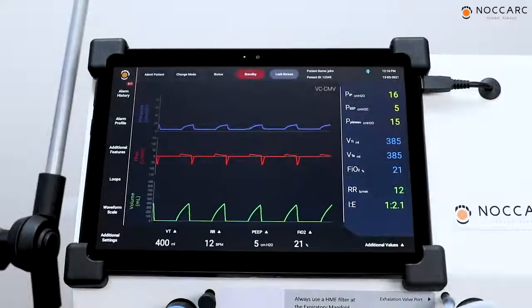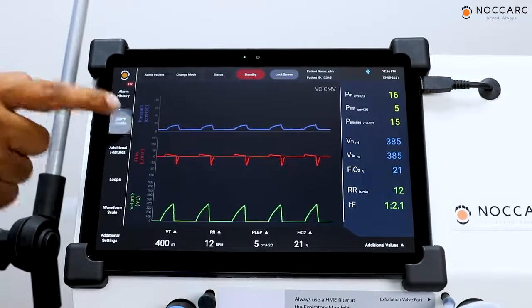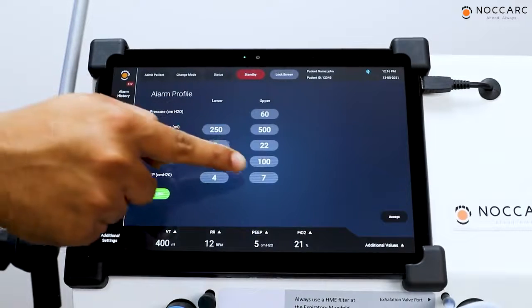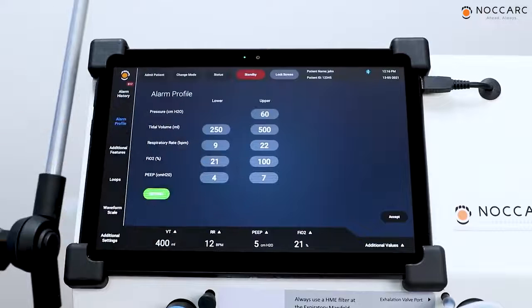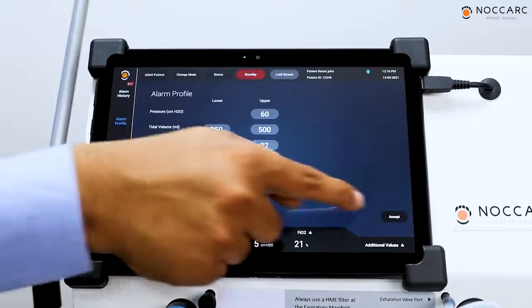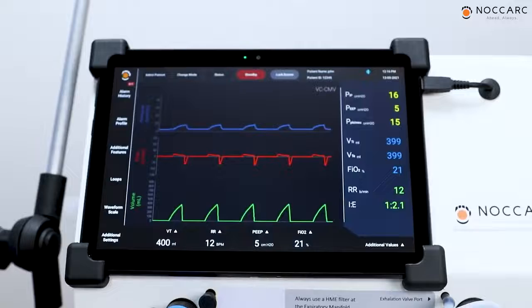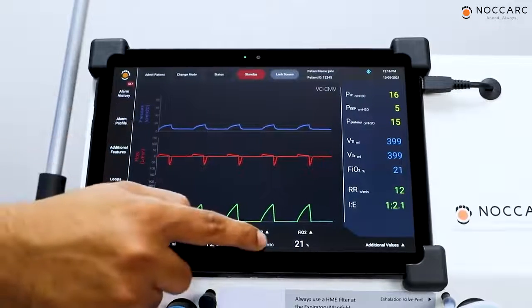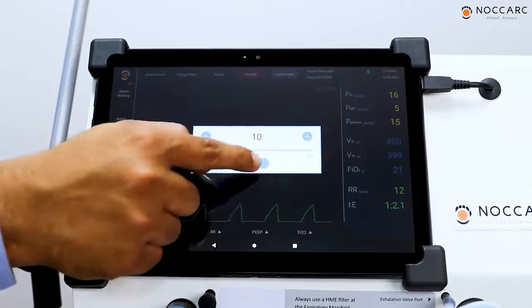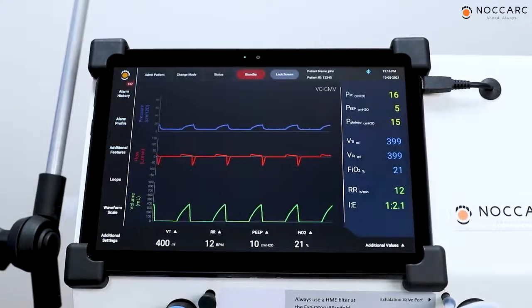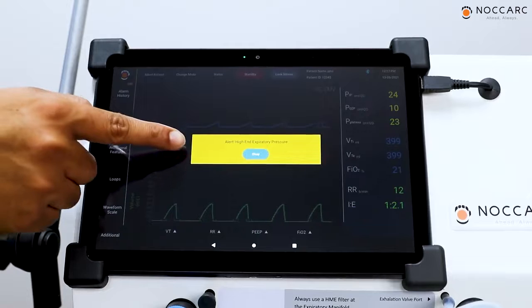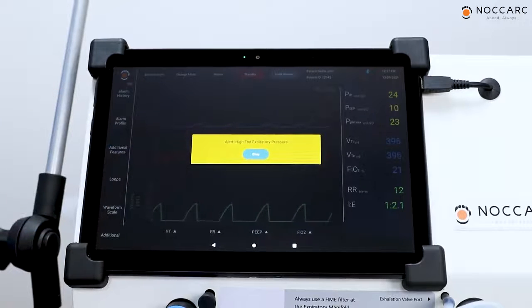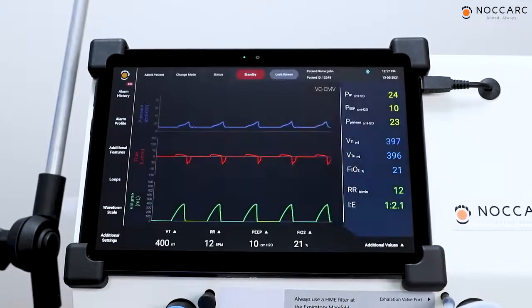To test high PEEP alarm, press on alarm profile. Upper limit for PEEP is 7 cm of water. Press on accept. Now set the PEEP value more than 7. Accept it. Here you can see high end expiratory pressure alarm is showing on the screen. That indicates PEEP value is exceeding the upper limit of alarm profile.